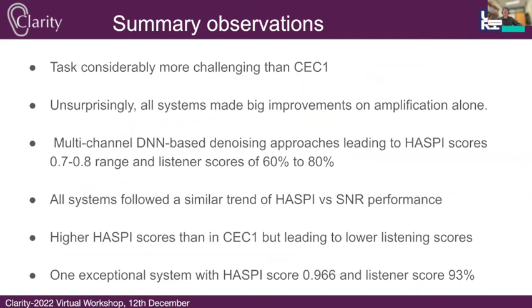To summarize: the task is considerably more challenging than CEC1. Unsurprisingly, all systems made big improvements over the amplification-alone baseline. Multichannel DNN-based denoising approaches led to HASPI scores in the range of 0.7 to 0.8 and listener scores in the range of 60–80% words correct. All systems followed a similar trend of HASPI versus SNR performance. We're seeing higher HASPI scores than in CEC1, but leading to lower listening scores, possibly because teams have more aggressively optimized for HASPI. One exceptional system achieved a HASPI score of 0.966 and a listening test score of 93%.